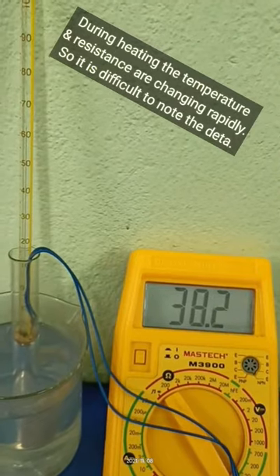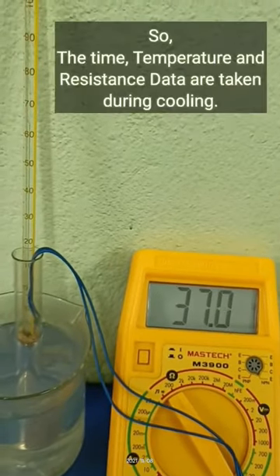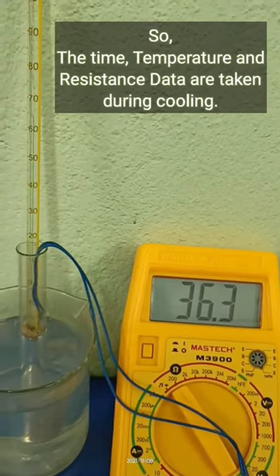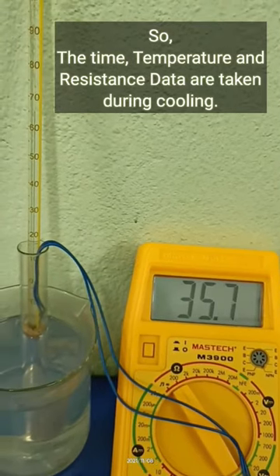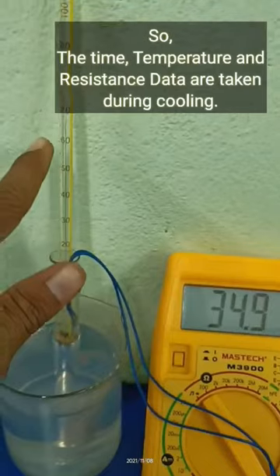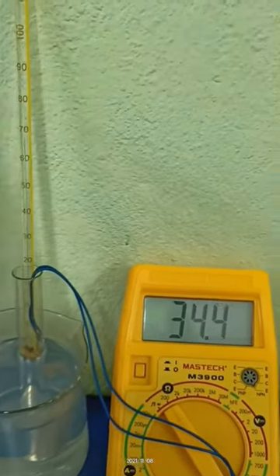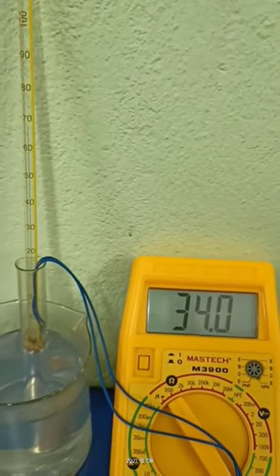Plot graph between ln R equals Y and 1 slash T equals X. The straight line graph Y equals MX plus C would be obtained. This is calibration curve for the given thermistor. It may be different for different thermistors.